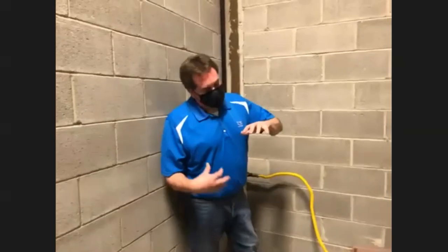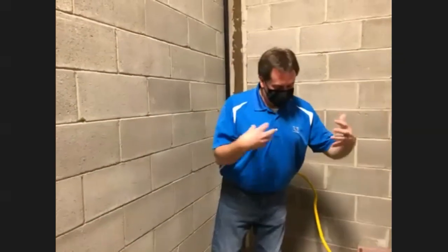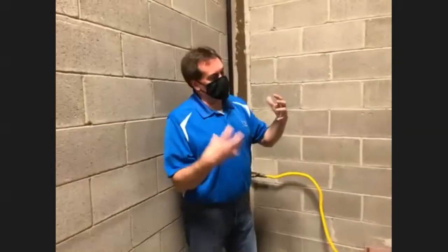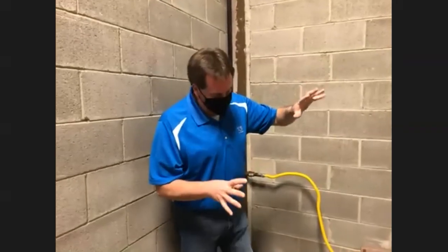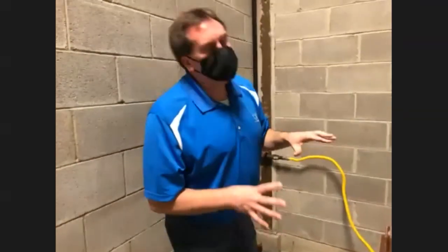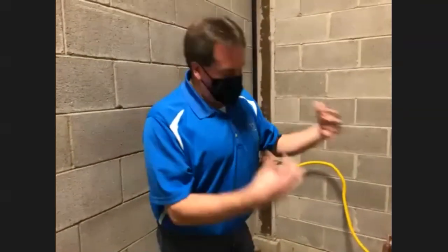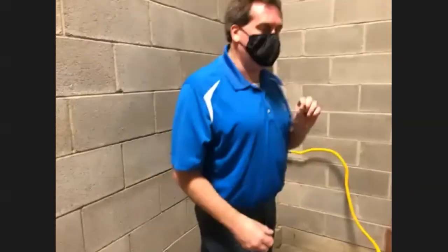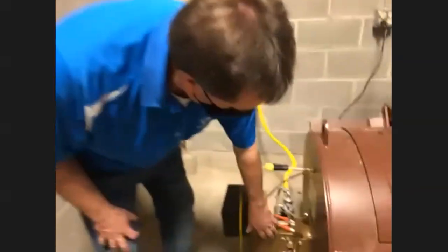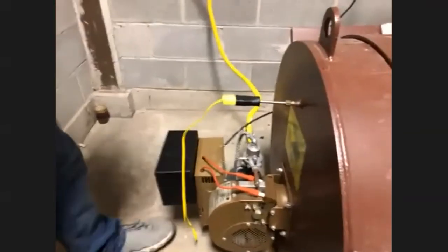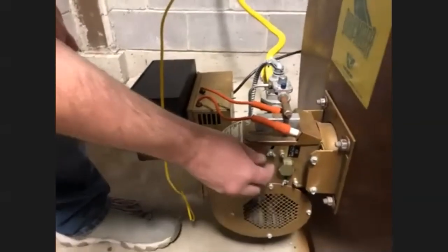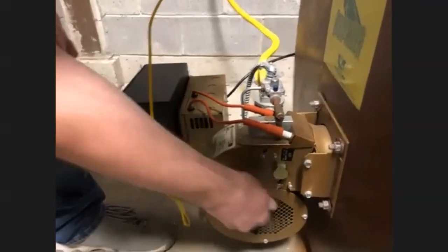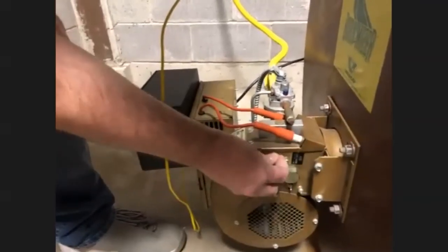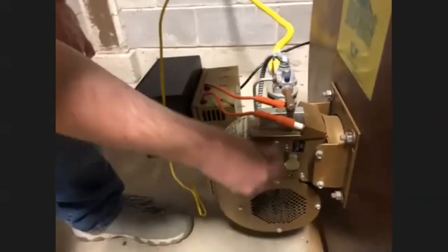So as the unit starts up, you see the flames inside, and you can get everything set accordingly. When you start things up and start firing, you also need to verify you have the proper air mixture. Right now we have what they call air bands. They have little wing nuts on here. These are your air bands that you adjust to control how much air is coming in, okay?